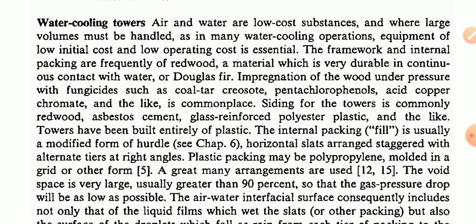water, or Douglas fir, impregnated under pressure with preservatives which resist fungus, such as coal tar creosote, pentachlorophenol, acid copper chromate, and the like, is commonplace. Siding for the tower is commonly redwood, asbestos cement, glass-reinforced polyester, plastics, and others, as is usual for cooling water tower equipment.